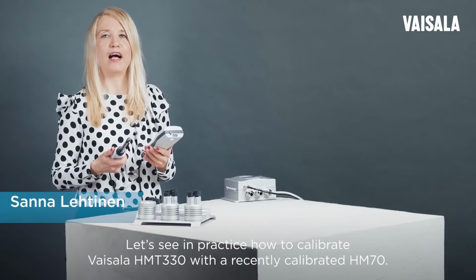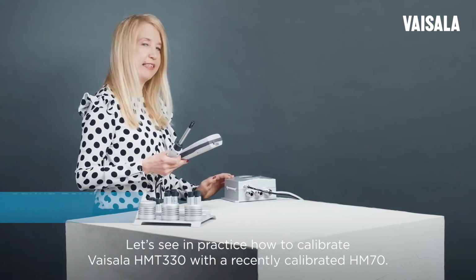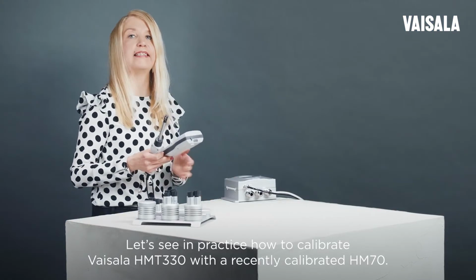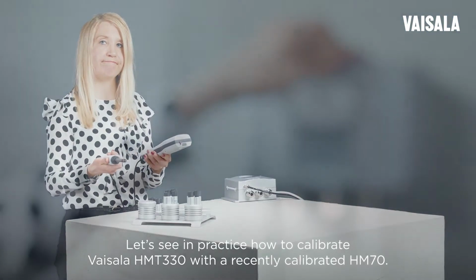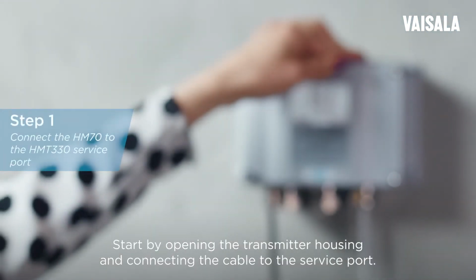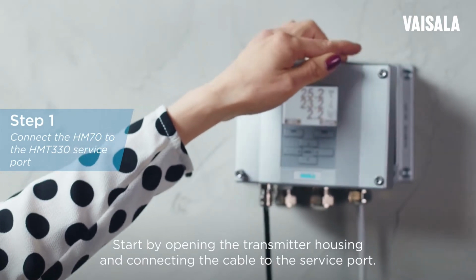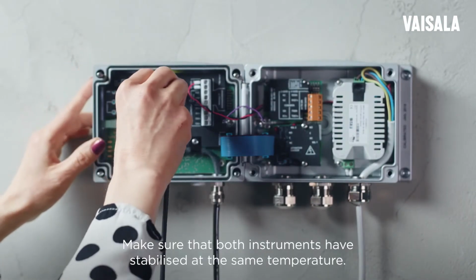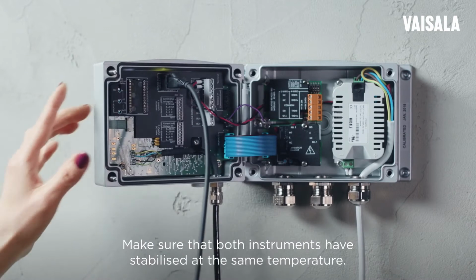Let's see in practice how to calibrate Vaisala HMT330 with a recently calibrated HM70. Start by opening the transmitter housing and connecting the cable to the service port. Make sure that both instruments have stabilized at the same temperature.